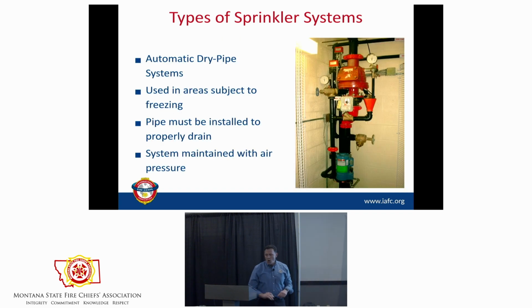So we have all these different types of sprinkler systems. We have them where they're dry, so areas subject to freezing. And basically in those dry pipe situations, you get this different valve configuration on the sprinkler. So do you see this thing right here that's circled in red? This is wet. This is water all the way to this point. And through the magic of engineering, less pressure of air holds back that valve. And when the sprinklers trip, the air pressure gets low enough, it releases, and 60 seconds later, water comes out.